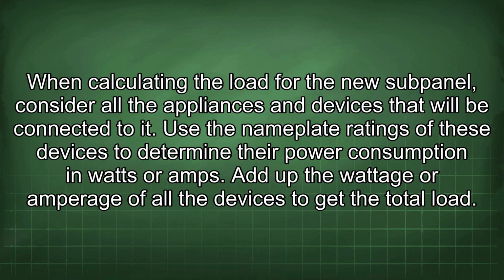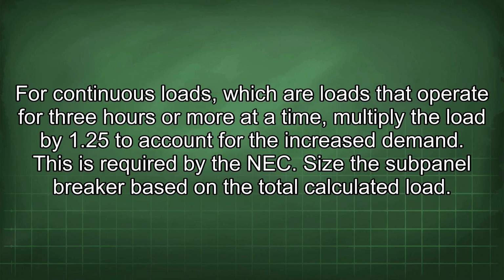When calculating the load for the new subpanel, consider all the appliances and devices that will be connected to it. Use the nameplate ratings of these devices to determine their power consumption in watts or amps. Add up the wattage or amperage of all the devices to get the total load. For continuous loads, which are loads that operate for 3 hours or more at a time, multiply the load by 1.25 to account for the increased demand. This is required by the NEC.